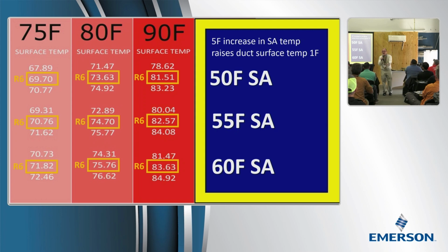How much will I raise the temperature of the ductwork so that it won't sweat? Can I get it above the dew point? Is what you're trying to do. I'm trying to warm this duct up. Well, if I speed up the air so that I got 60 degree leaving air, now, that's not great for many reasons, but I got 60 degree leaving air. I only gained 2 degrees. The duct's only 2 degrees warmer. So you have to change the supply air temperature by 10 degrees to get a 2 degree difference. You've got to change it by 5 degrees just to get 1 degree. So that's all that poor service technician can do.